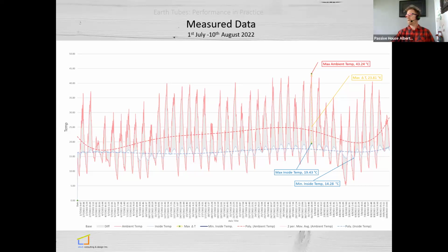Okay, thank you. Rob's asking a bit more: is there actually a calculation for how long the earth tube needs to be, or do we just say at least 100 meters and longer if possible? Well, again, you can use the WUFI software, or you can use the PH Luft to calculate or to get a rough number. Other than that, to keep it simple, I would say everything that's longer than 100 feet doesn't really do a lot anymore. So 100 and as deep as you can. That would be my recommendation. But again, it all depends on the ground.